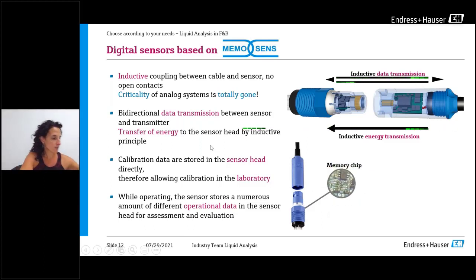Now, in these times that digitalization is so important, we will speak about something that E+H developed more or less 15 years ago, and that was the digitalization of the value that I measure. This started with pH, because the pH is measured in millivolts, and with these millivolts we enter an equation that gives us the pH. When these millivolts are 0, so when I don't have current, I have pH 7. So in the case that in the installation the cable was cut, or the connection between the sensor and the transmitter, that is this cable, for example because of humidity, is corroded, and then we don't have any current, then I would also measure 7.